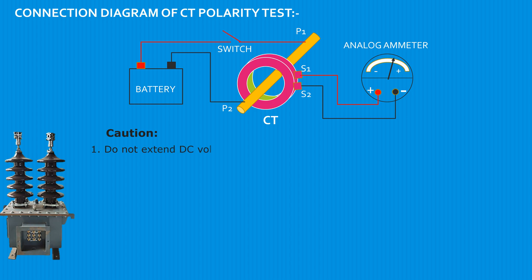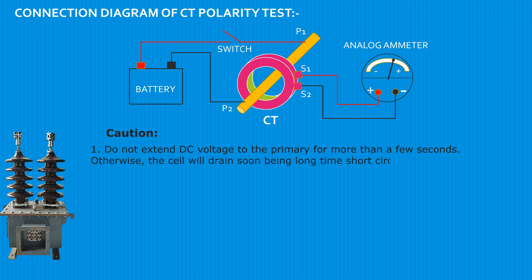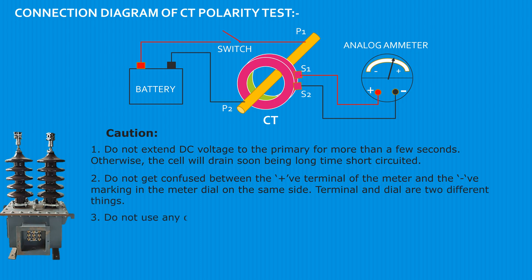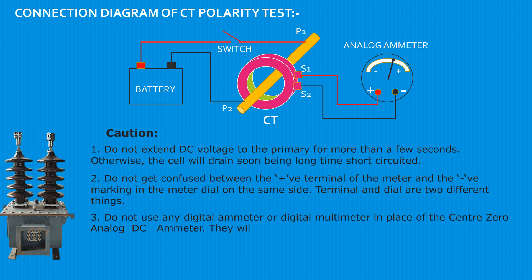Do not apply extended DC voltage to the primary of the test CT. Do not use any digital ammeter or digital multimeter in place of a center-zero analog DC ammeter, as they will not serve the purpose of this test.